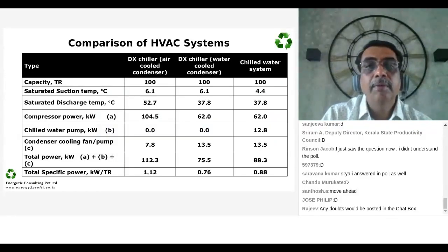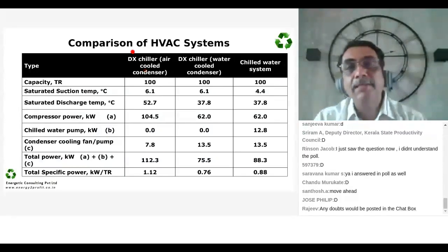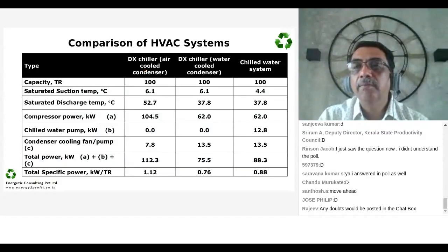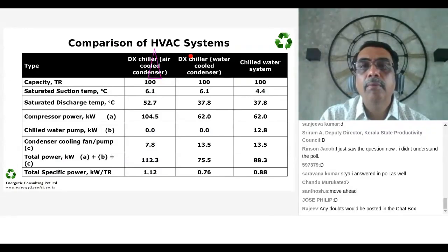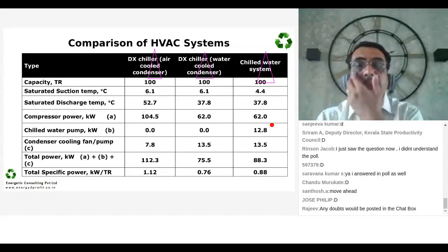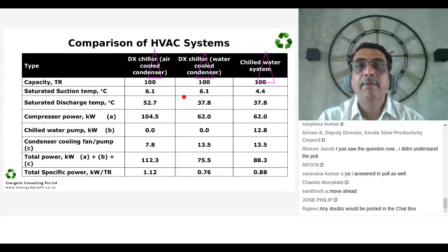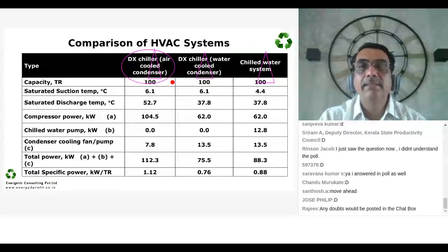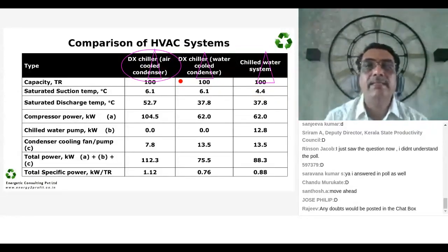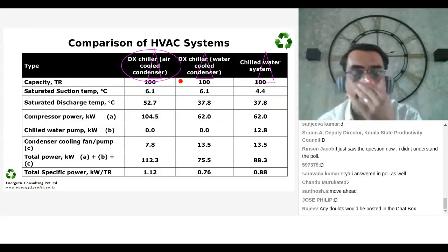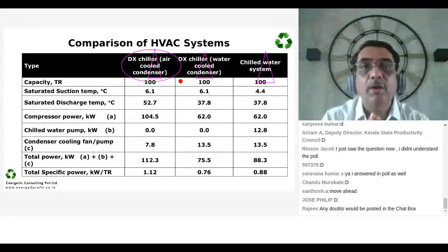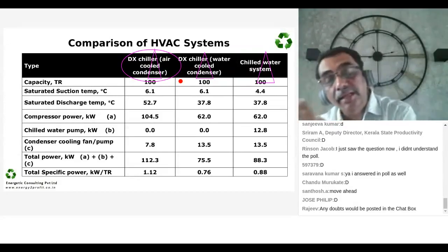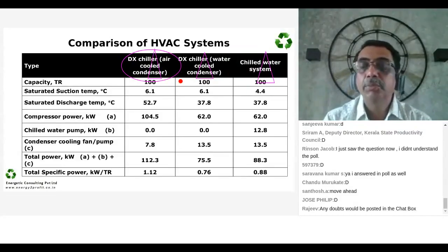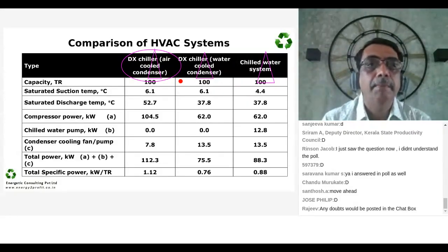Now, comparison of the options based on what kind of system we are choosing. First we saw what kind of compressors. Now we are looking at what kind of system. Say for example, DX system means that the refrigerant is directly cooling air. And when I say air cooled condenser, I am saying the condenser side is cooling air, which means ambient air is cooling the system, right?